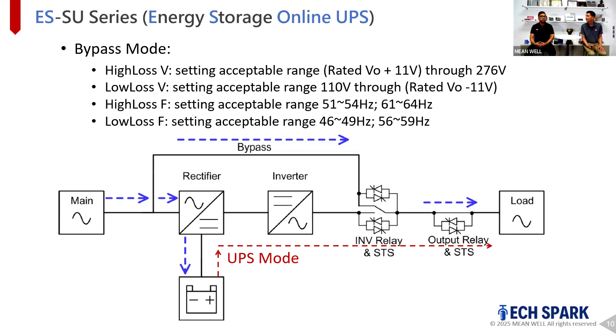Cool, so that is bypass mode, and the next one is what we call AC mode. You see the blue line flow from AC in, rectify the voltage, charge the battery, then invert to AC and go to the load. So this is really a double conversion, and under this mode the efficiency is not that high because there's a loss between the rectifier and inverter, but the transfer time is 0 - meaning when there's a power outage, the load won't see any loss of power in any second.